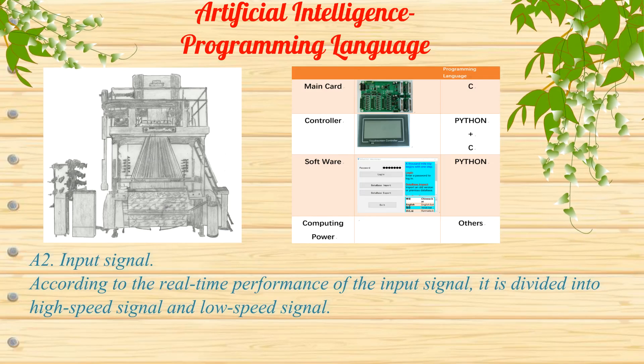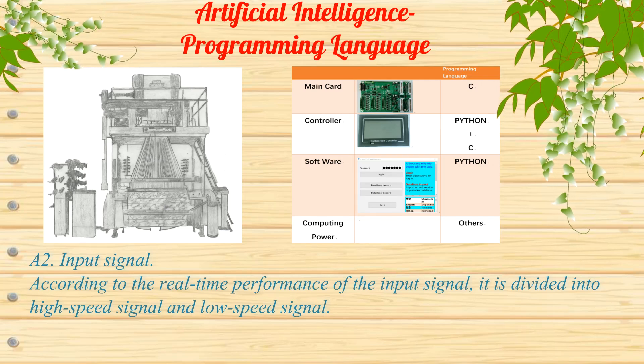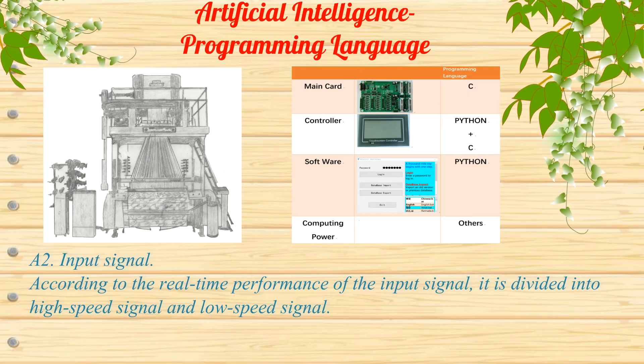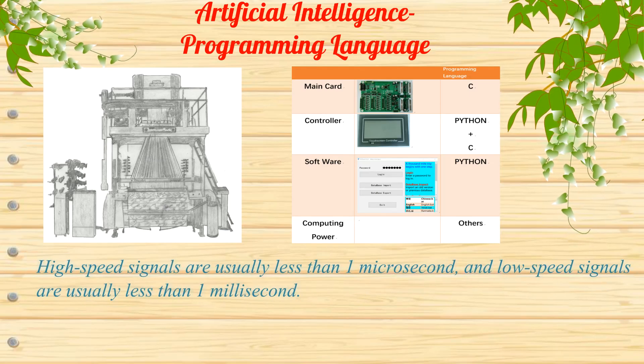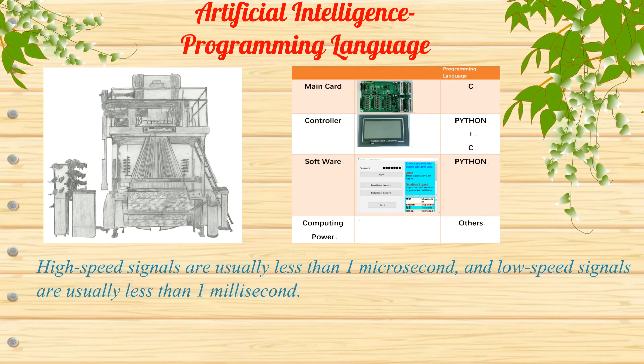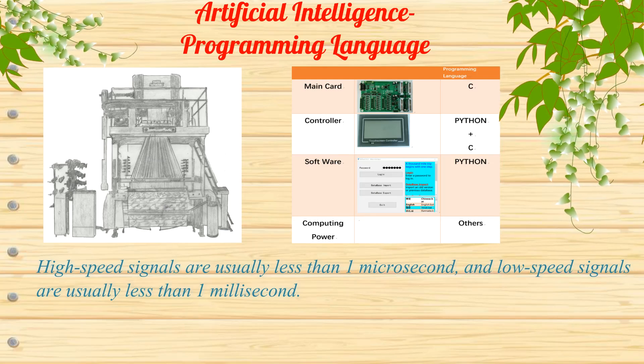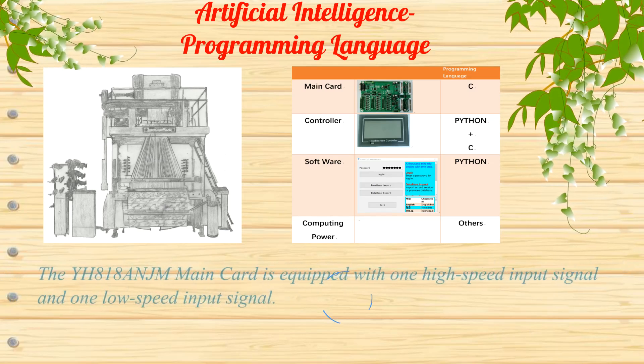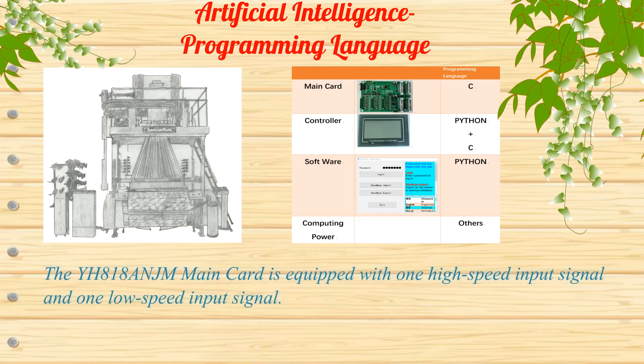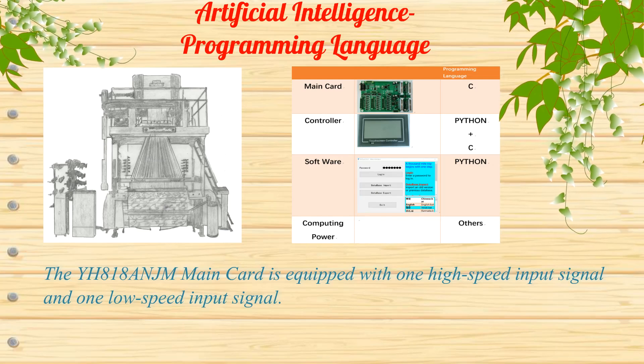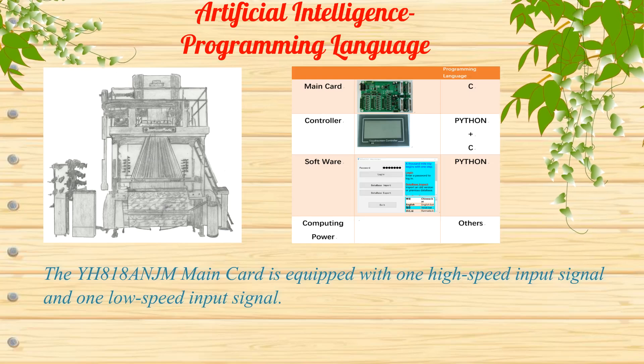2. Input signals. According to real-time performance, input signals are divided into high-speed and low-speed signals. High-speed signals are usually less than 1 microsecond, and low-speed signals are usually less than 1 millisecond. The YH-818-ANJM main card is equipped with 1 high-speed input signal and 1 low-speed input signal.